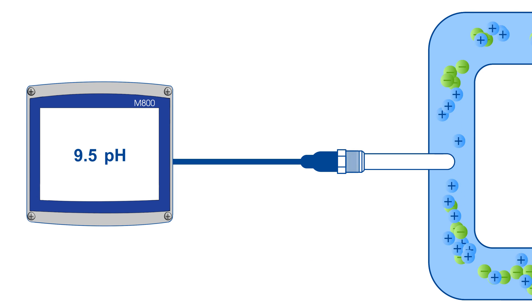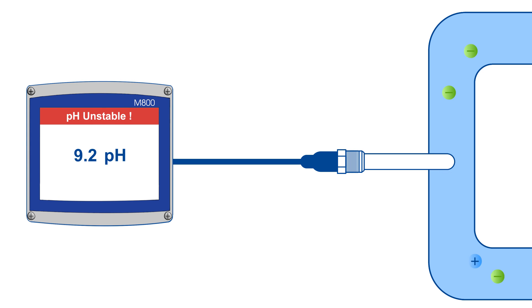However, in high purity water and steam, there are not enough ions in the water to generate a pH response, causing the pH reading to be unstable.